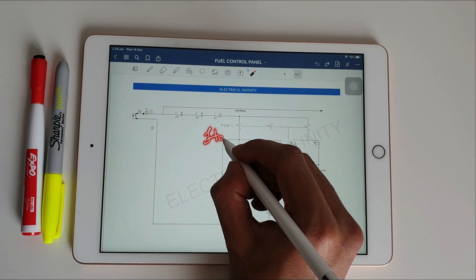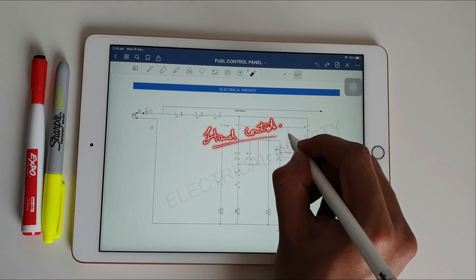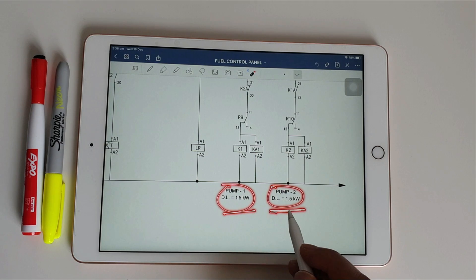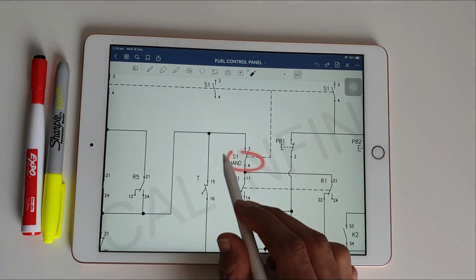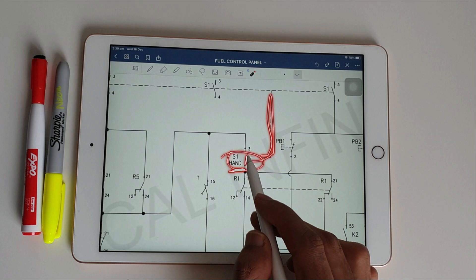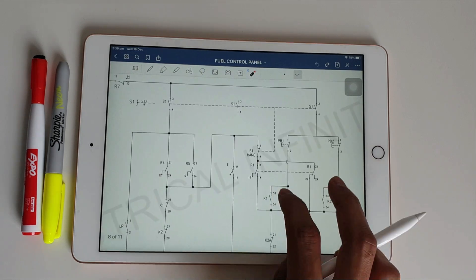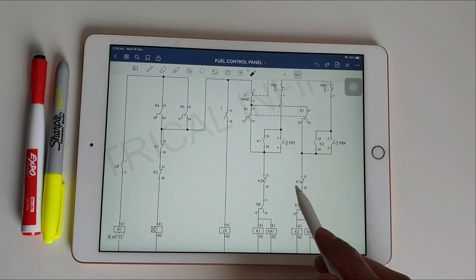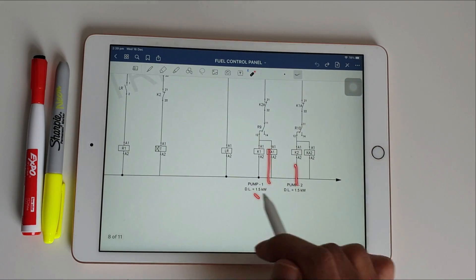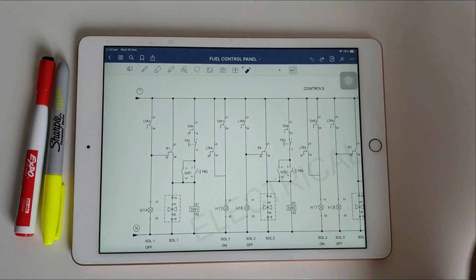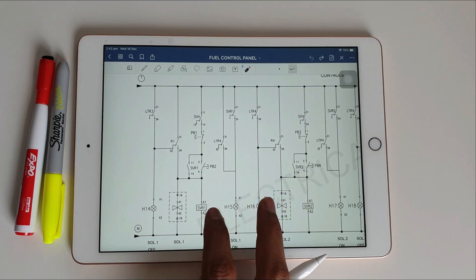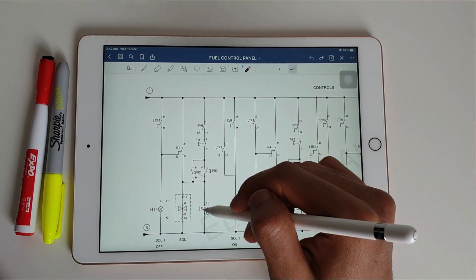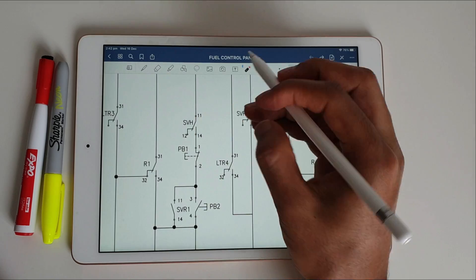For pump operations, the right side shows hand control and the left side shows manual control. Pump one and pump two are shown. When selector switch S1 is turned to hand mode, it passes supply to the R1 relay terminals, the NO becomes NC, and when we press the push buttons the supply passes through K1 and the pump turns on.